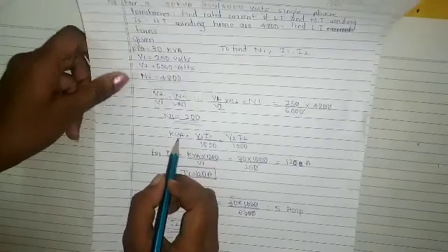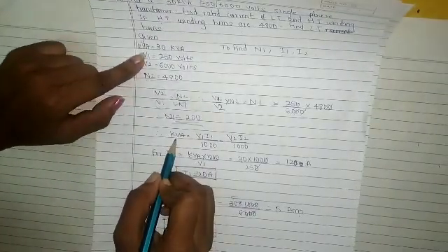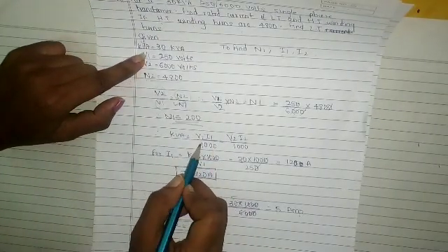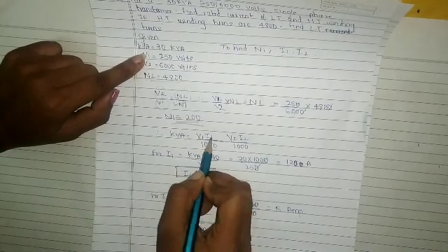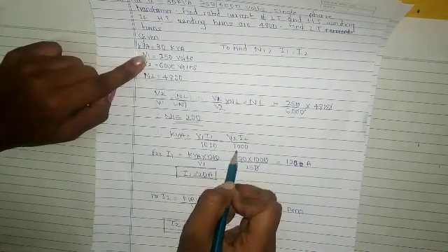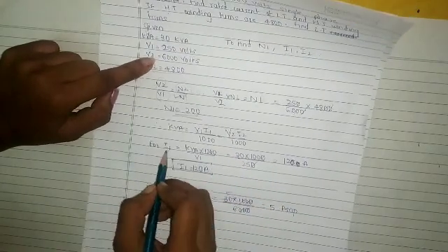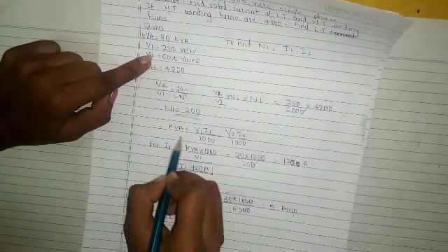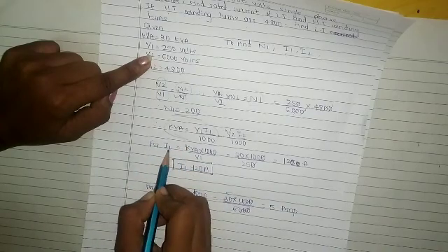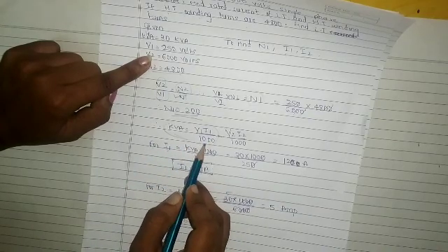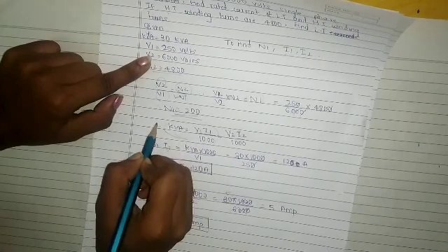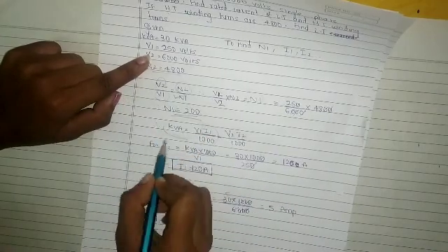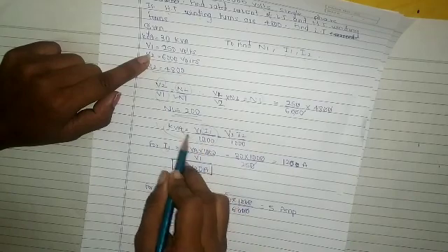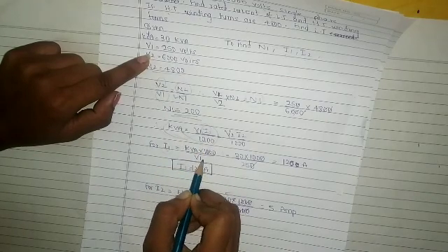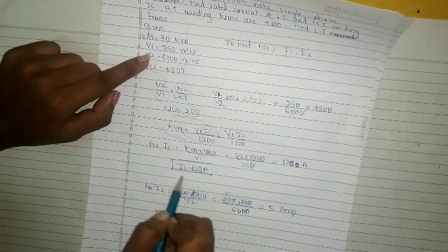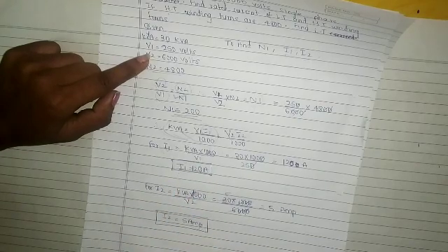Now, using the given kVA, we have to find I1 and I2. kVA is equal to V1 I1 divided by 1000, which is equal to V2 I2 divided by 1000. For primary current I1, we rearrange to get I1 equals kVA into 1000 divided by V1. Substituting the values, we get the answer as 120 ampere.